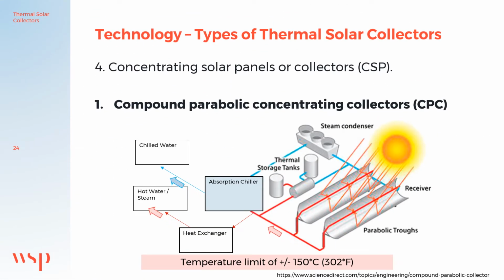The heat generated by the CPC is typically provided to either an absorption chiller to provide chilled water to a building or industrial process, or the heat can go through a heat exchanger to provide hot water or steam.